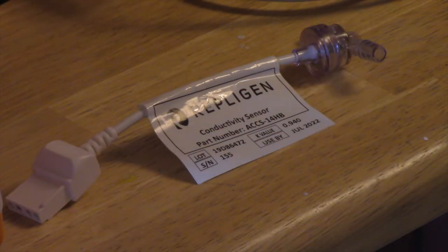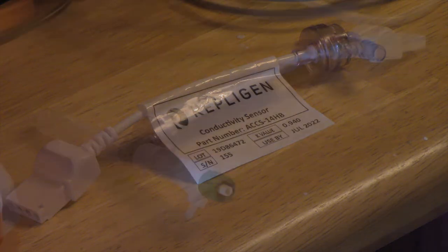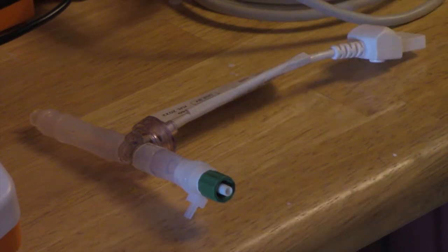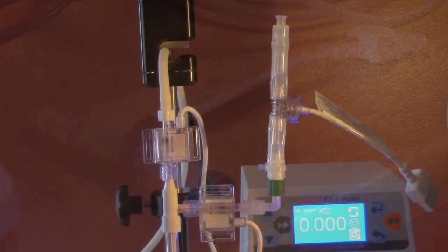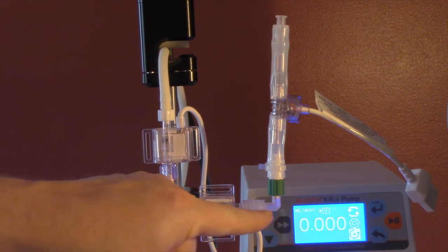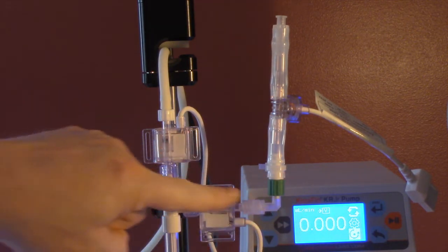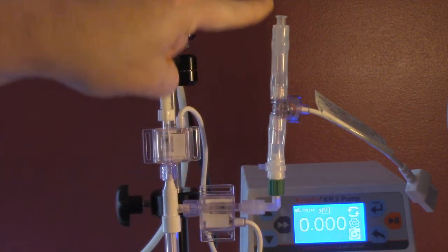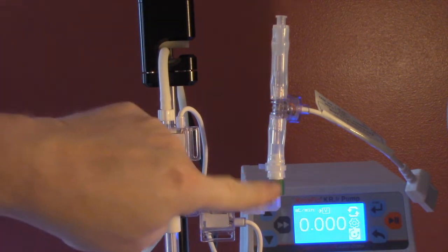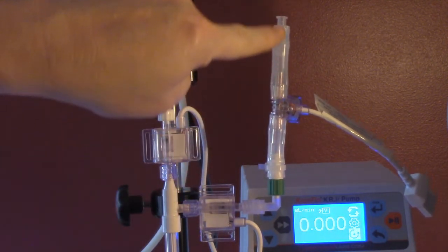Each conductivity sensor has a unique K value which must be input into the computer. Also notice that each sensor has hose barb fittings and we must convert those to luer lock. On each side of the probe I put a piece of size 15 tubing, also with a luer lock fitting, so that we can connect this up to the permeate. Coming off the permeate I put an elbow so that if there's any air trapped in the system, the air will expel out through the top. And here's my sensor, so it's going to travel straight through.